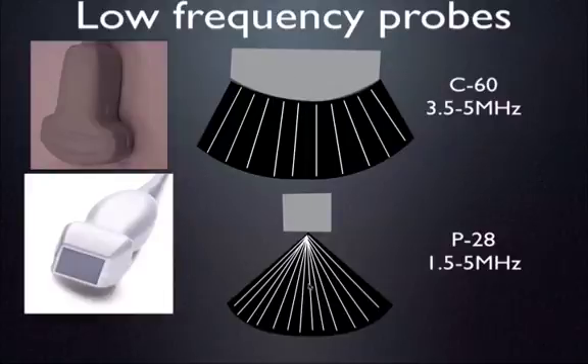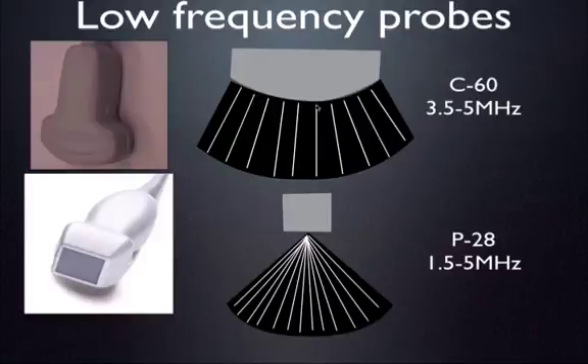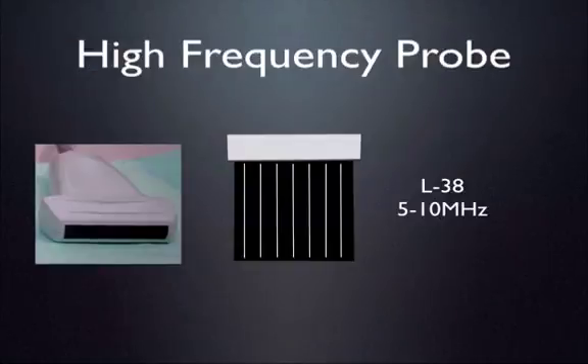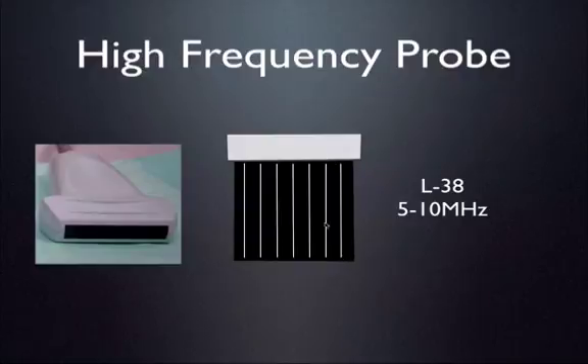One key difference between the cardiac and abdominal probes: the cardiac probe is a phased array probe, meaning sound waves originate from one point and are steered out into space, rather than originating from a wide surface area in parallel fashion like the abdominal probe. The high frequency linear probe — the L38 — is 38 millimeters across and operates at 5 to 10 megahertz, with multiple channels producing parallel sound waves. Being high frequency, it offers shallower penetration but much higher resolution.